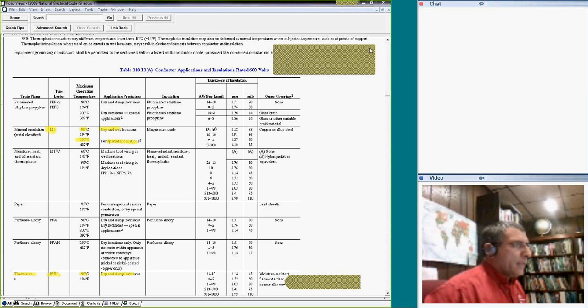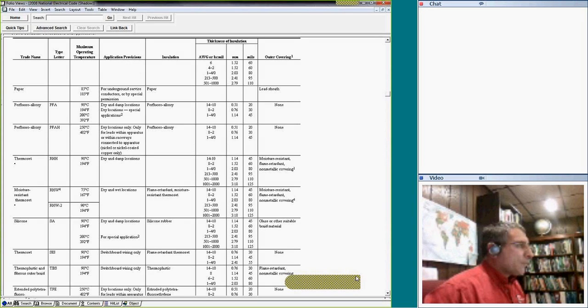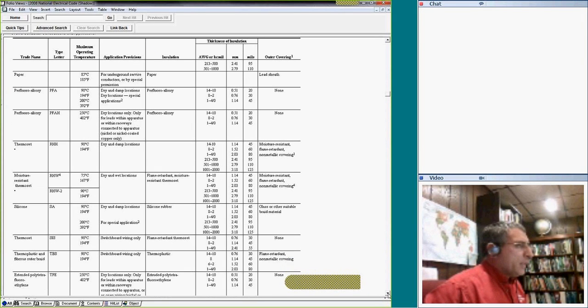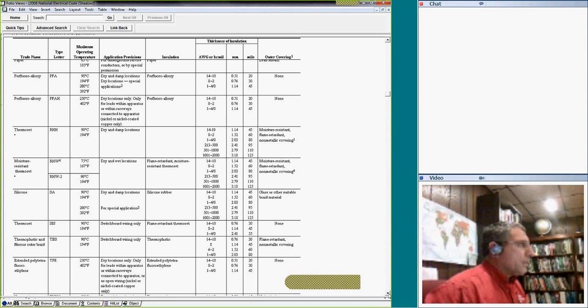Damp location. Where you find the installation, let's go to RHH. Okay, here you go. So again, RHH, you can only use it in a dry or damp location. It's rated for 90 degrees. If I use, let's say, SA cable, SA cable is rated for 90 degrees, but remember, dry or damp location.